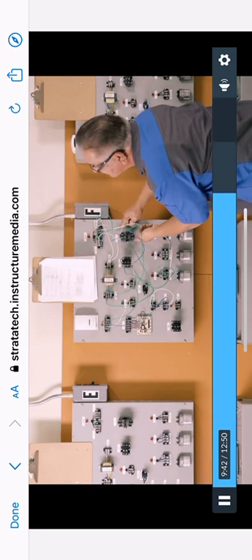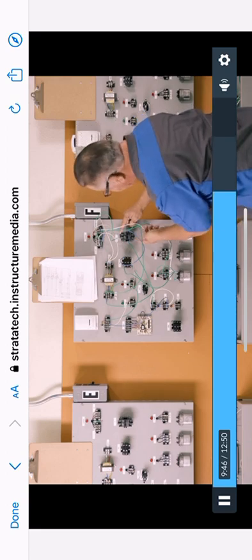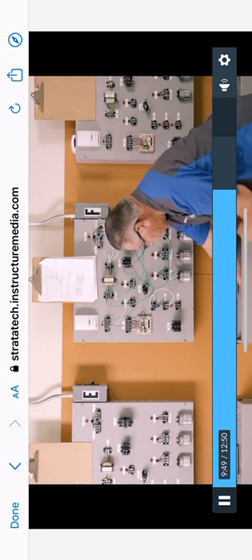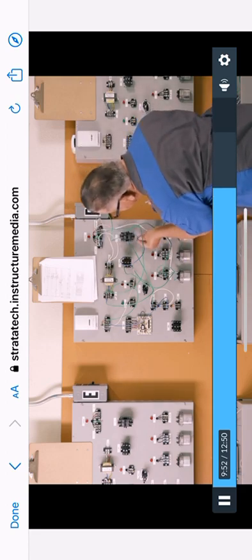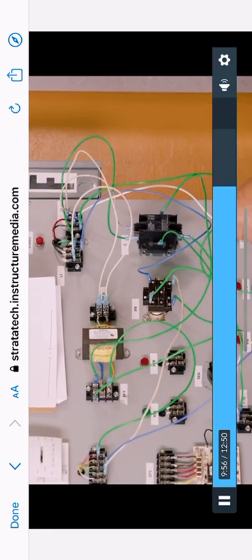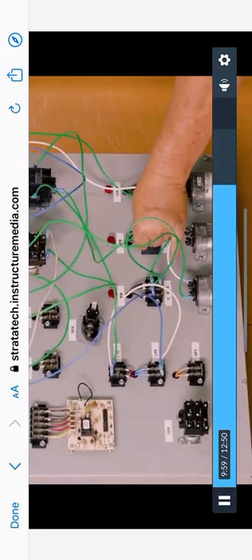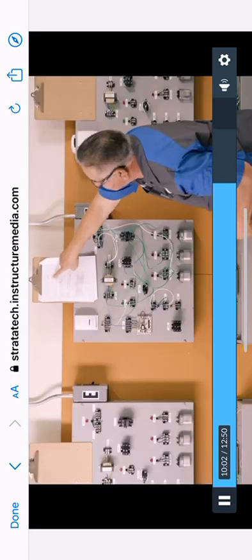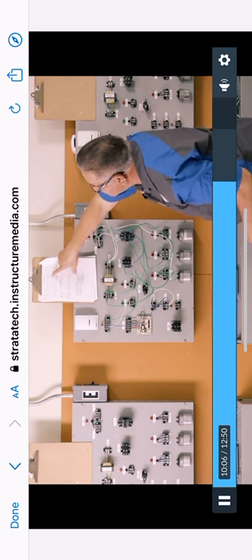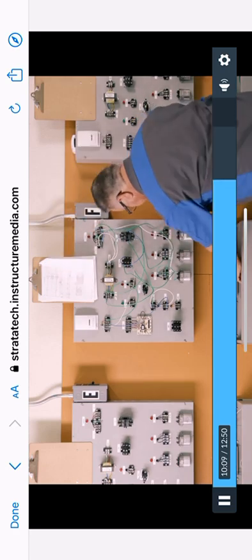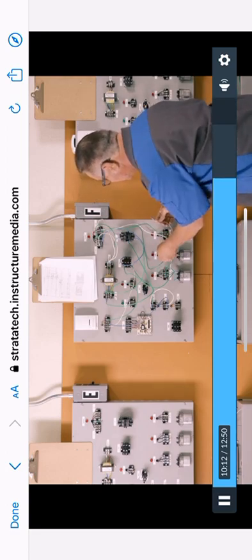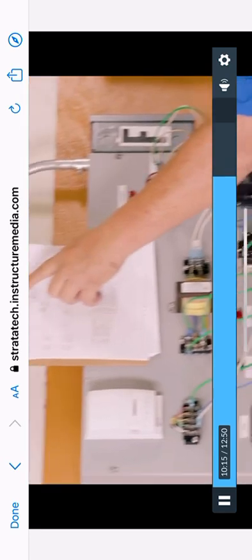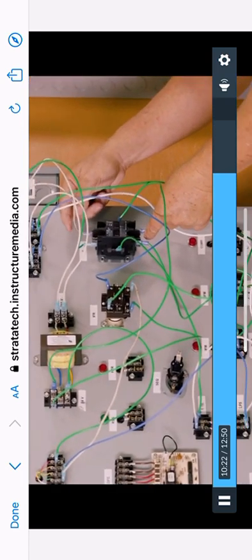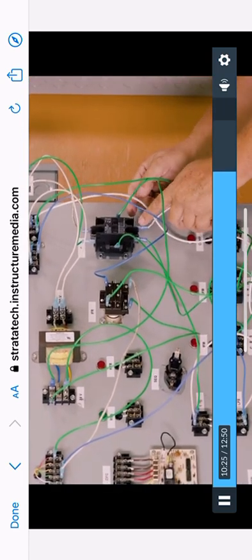I'm going to come off of here, and I'm going to go to the common of the outdoor fan motor. So I'm going to get a wire, and I'm going to put it from here, the bottom of the contactor, which is T1, and I'm going to go straight to my common on my outdoor fan motor. I just ran this wire to there. I'm going to come out of my run of the outdoor fan motor, which is this one here. And I'm going to go to my T2, which is right here underneath the contactor. That's line 2. This is T2. This is the bottom.